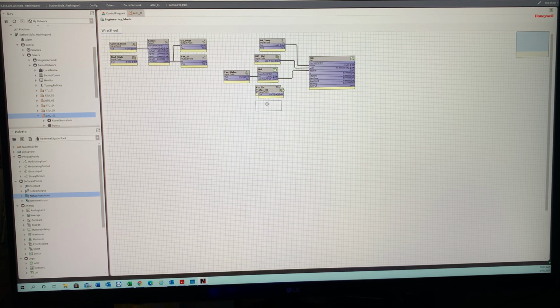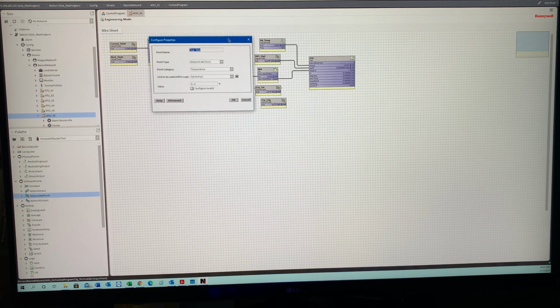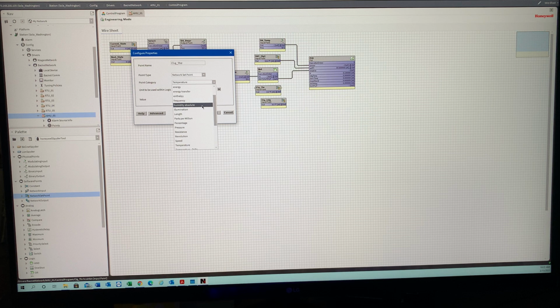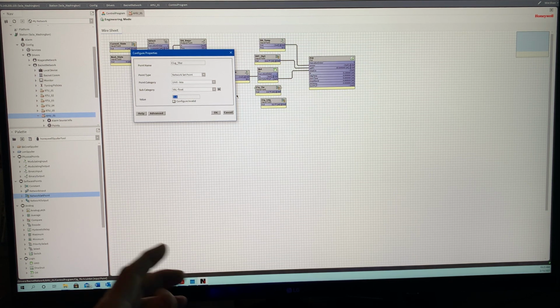So we're going to configure the properties on these - throttling range, configure, I'll bring it over here. We're going to make this unitless valve float. I like to keep a pretty consistent basis to start off with, normally around 8 to 10, depending on what you're trying to control. For this application, I'm going to do an 8.